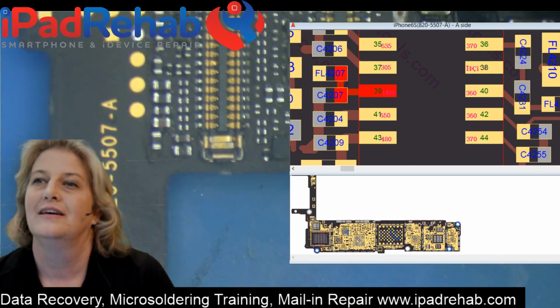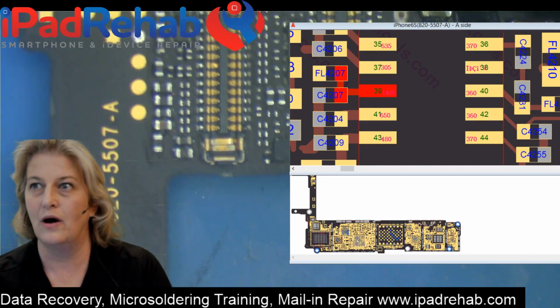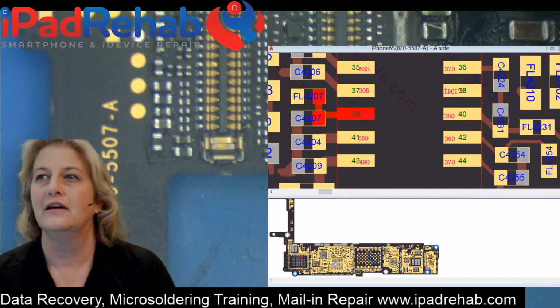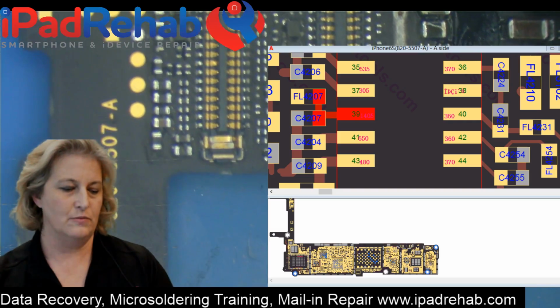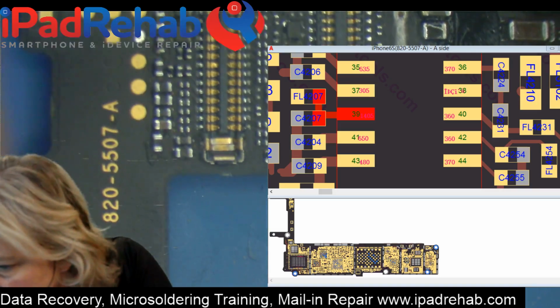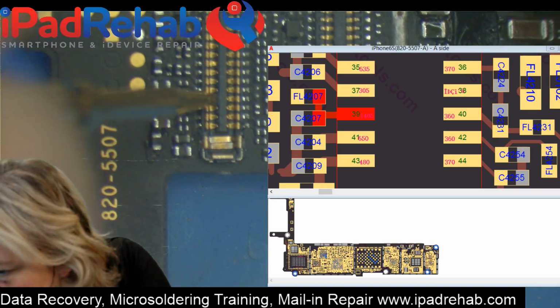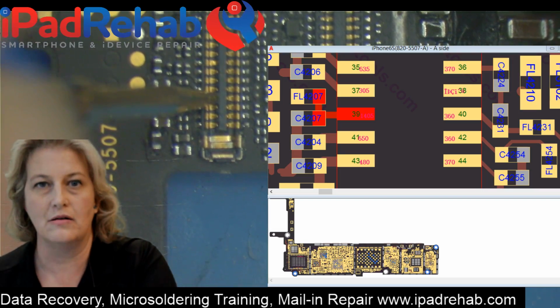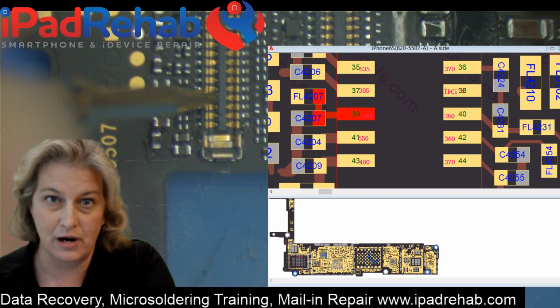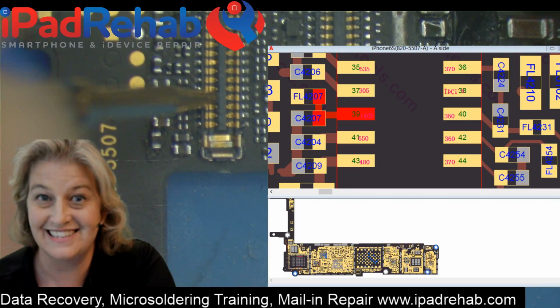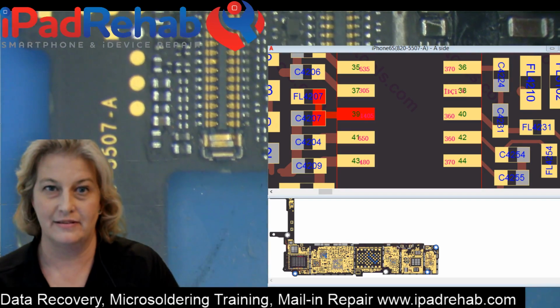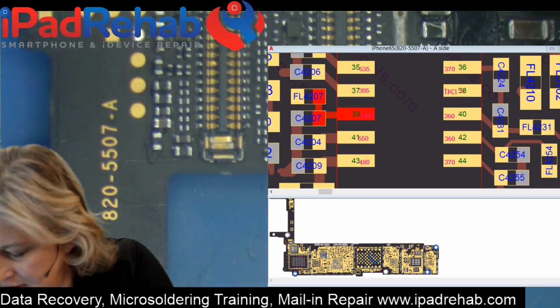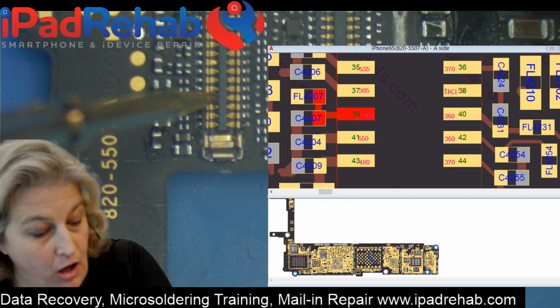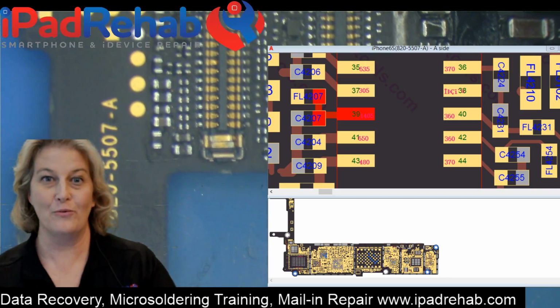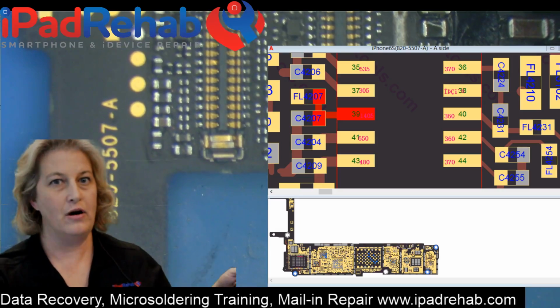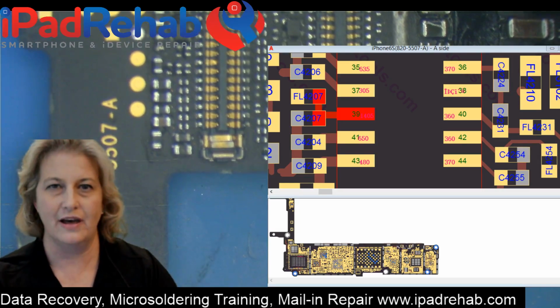So we're going to just deftly cross around that, and we're going to go up to line number 4. So the fourth line here is supposed to be 0.305. Let's see, what is it? Red probe on ground. Line number 4 is, survey says, OL. That is an actual problem. So now we've got OL instead of 0.305. That's a big deal. And we can even prove that by going in our reverse direction, OL. So no matter what you do, there is an open on this line somewhere. So now we've got an actual problem.